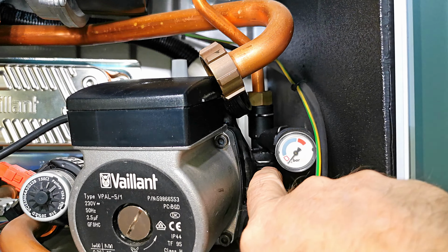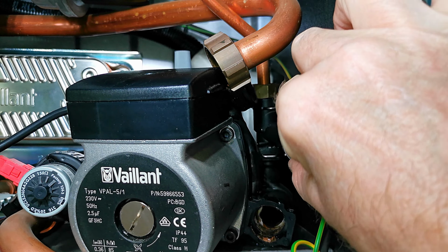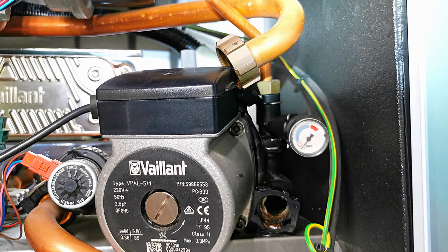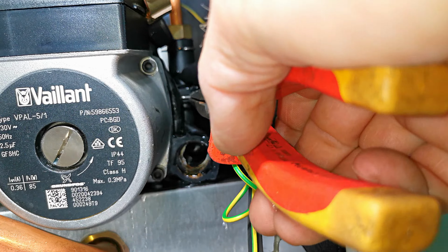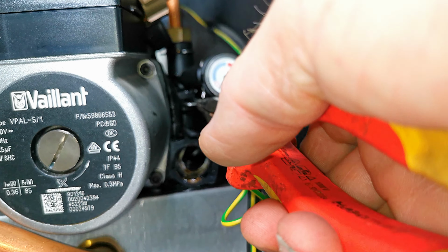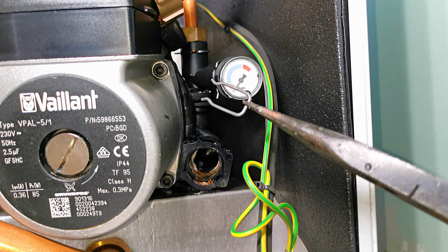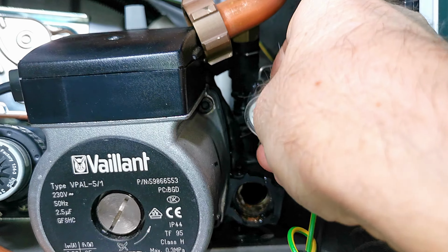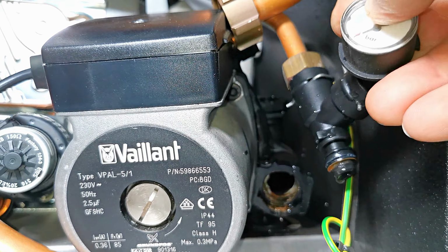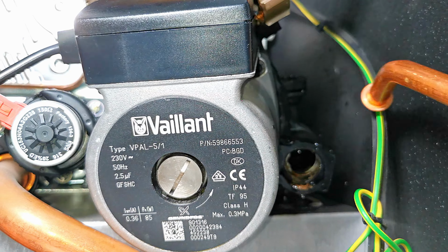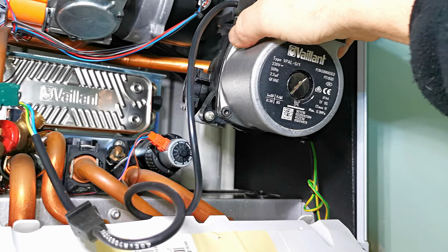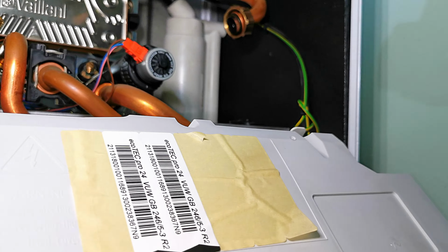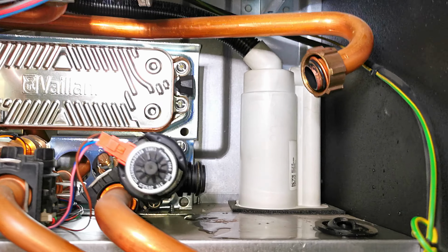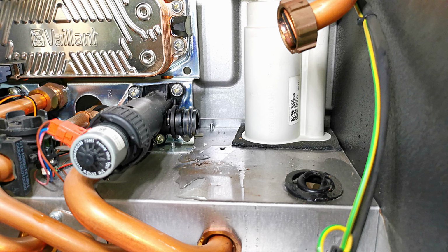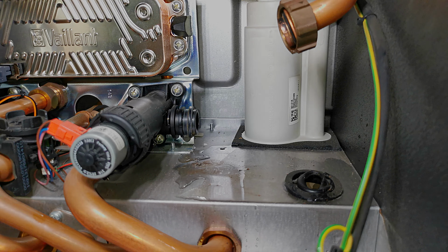So to easily get the pump out, I just need to remove the pressure gauge. So I'm going to remove that clip on the bottom there. So I just get my long nose pliers and just pull that clip out, and there we go. I now pull the pressure gauge upwards, giving it a wiggle to release it from the pump body. And there we go, that's that done. I can now just lift the whole pump assembly out of the boiler. And there we go. And I've done that without having to touch the diverter valve at all.